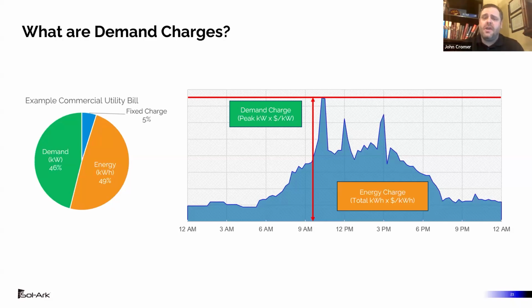Now, demand charges are basically the height of your load profile. What is the maximum instantaneous sliver of demand, whether it be 15 minutes or 30 minutes or 1 hour, of that facility over the entire month? That's a demand charge. Residential electric bills and time of day or time of use metering are energy charges. That's more like the area under the curve. And so there's a different strategy if your bill is mostly demand versus mostly energy that we're going to get into in the next slide.